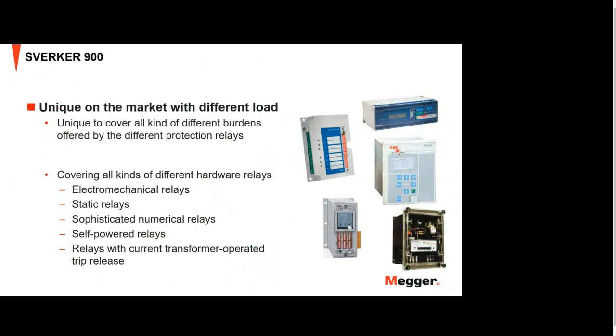So Sverker 900 is very unique in the market because it can cover testing different kinds of hardware in the relay protections, because the burden could be very different depending on what kind of hardware it is. So if you have the electromechanical relays, they have an inductive non-linear load, which is sometimes very difficult because you need to have a lot of power, and if you are on quite low current, like 1 or 2 amps, it's difficult to get that power at that very low current. But Sverker 900 can manage this.